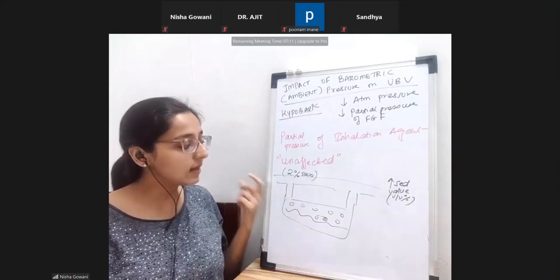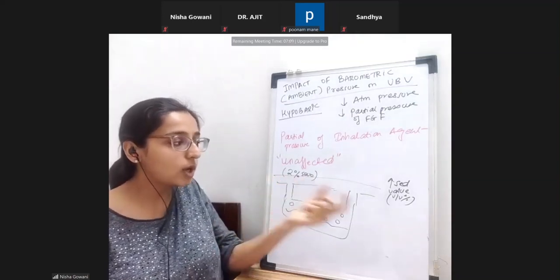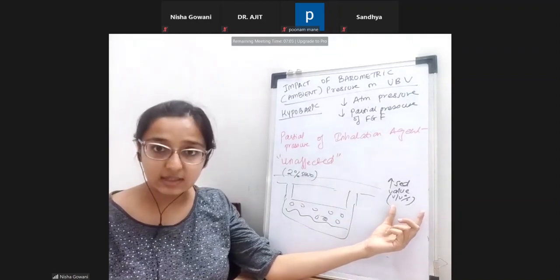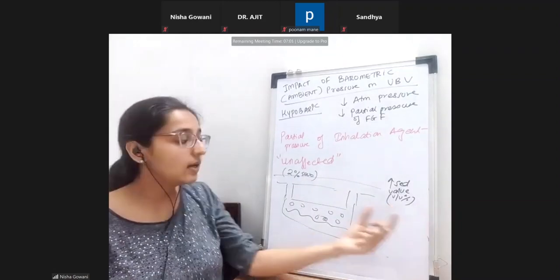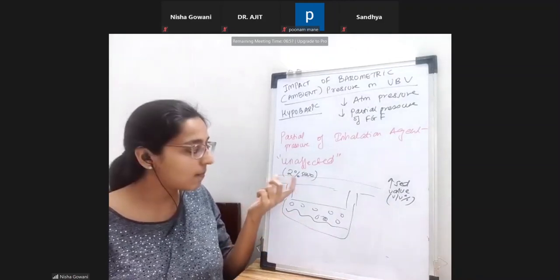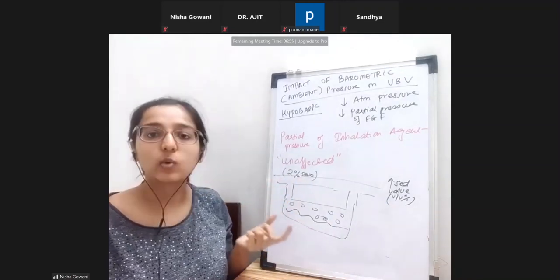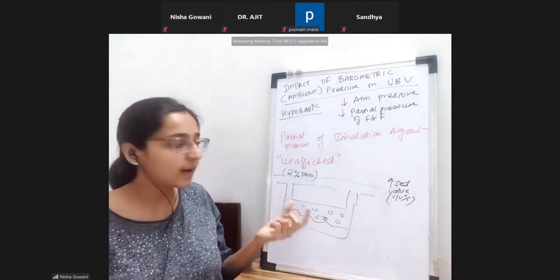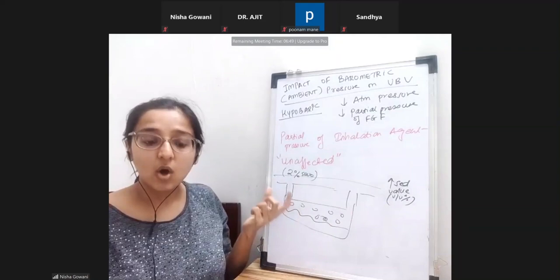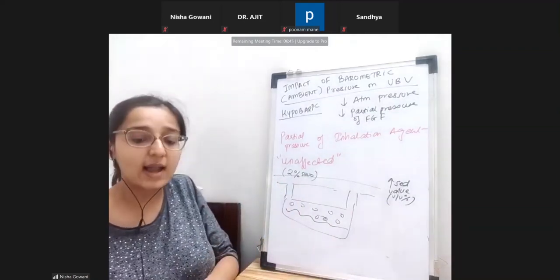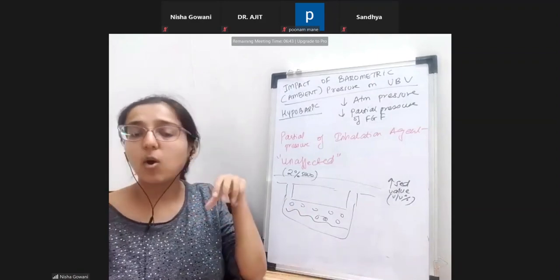So let's understand that although the volume percent shows an increase when we calculate it, in reality the partial pressure is still the same, and the amount which you have set is actually what is getting delivered. Although you might calculate and get more, the amount that you have set on the dial is what is getting delivered. And that's why when you go to high altitudes, you're not supposed to keep altering the dial.